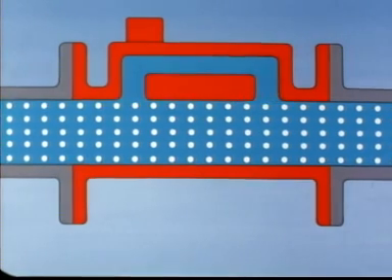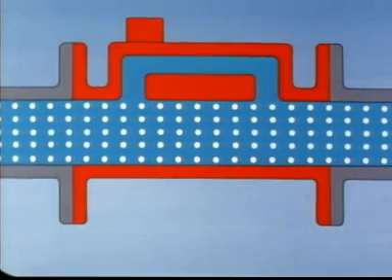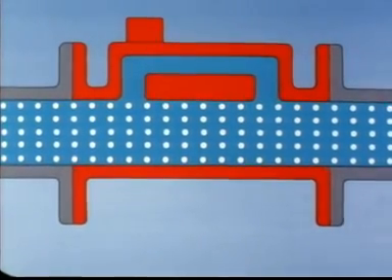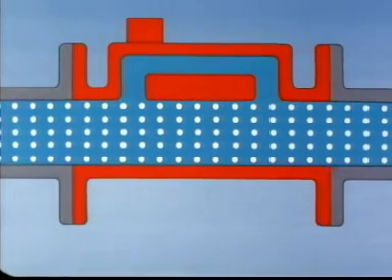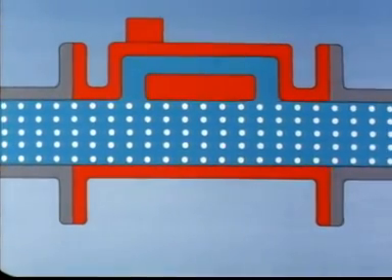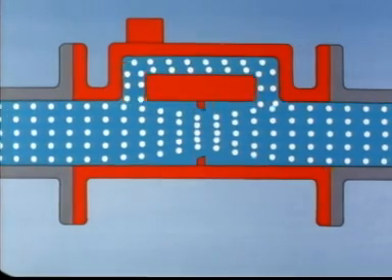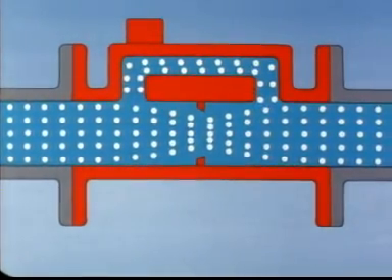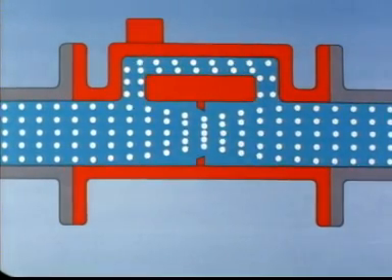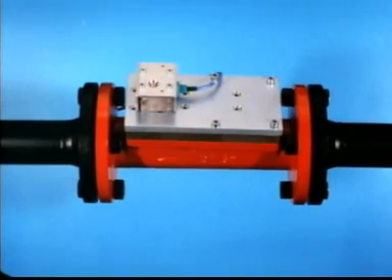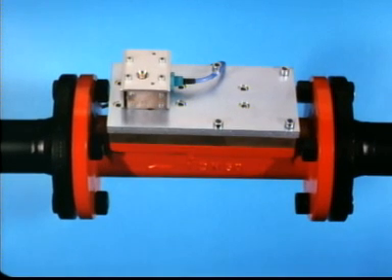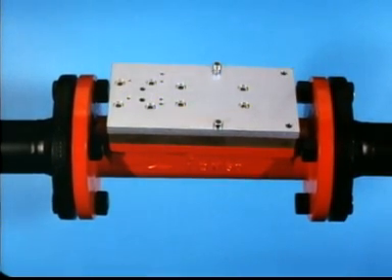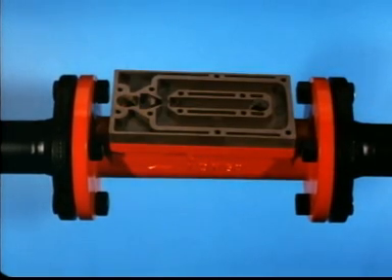The Fluidistor measures a partial flow which is proportional to the total flow. We obtain the partial flow by arranging a restriction in the main flow path, thus diverting part of the fluid through the Fluidistor. The sensing head can easily be opened to reveal the ingenious Fluidistor oscillator, which has no moving parts whatever.